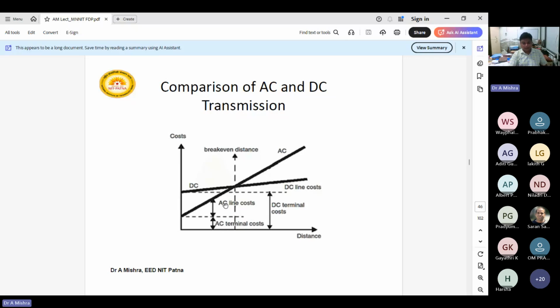But if you are going for the DC transmission, its terminal equipment cost is very high. Why very high? As I told, it will require a rectifier station. The rectifier station is not the rectifier you see in the lab. It generates thousands of, suppose, 400 megawatt power. So for a 200 to 400 megawatt rectifier, a single rectifier will be the size of a building. The rating of the devices and the rating of the conductors, all those things will be at a different level. So here the conversion of AC to DC is not what we look at in the lab. The introduction of a rectifier and an inverter in the system is basically the terminal cost, so that will increase. So the initial cost of DC transmission is very high. Initial cost you can also call the capital cost. That will be very high.